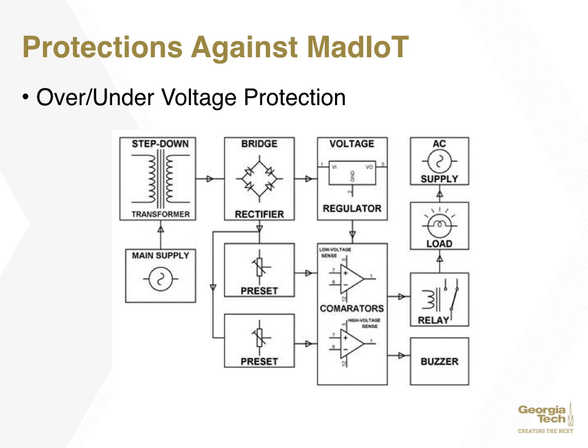The first is over-under voltage protection. This covers the scenario when a voltage of a bus is too low or too high. A voltage relay will be triggered after a set amount of time. This activation time depends on an equation modeling configuration thresholds and over-under voltage relay pickup values. All of this is an effort to protect local components, so that they don't allow their unit to operate outside the system frequency range of the system. So it will disconnect the units from the system to prevent damage.